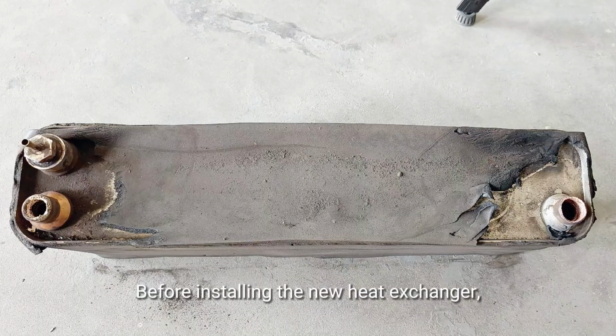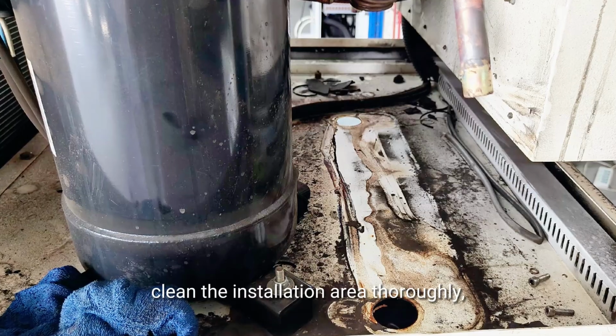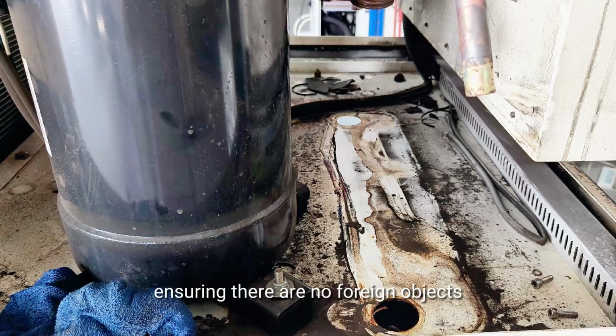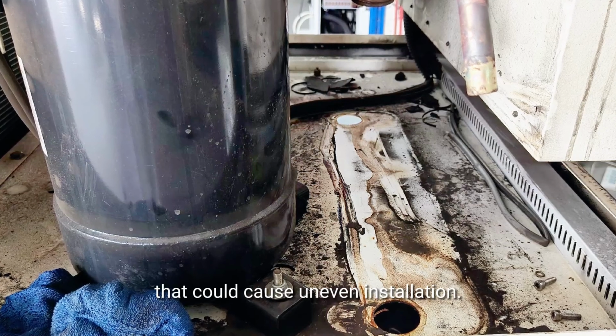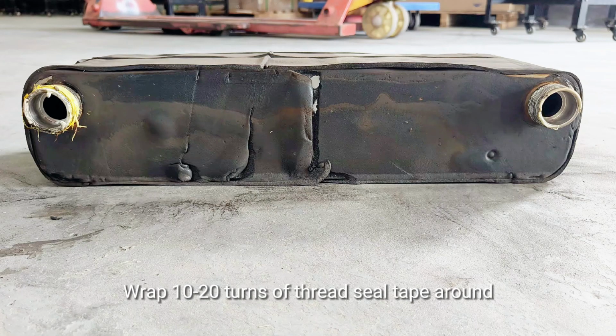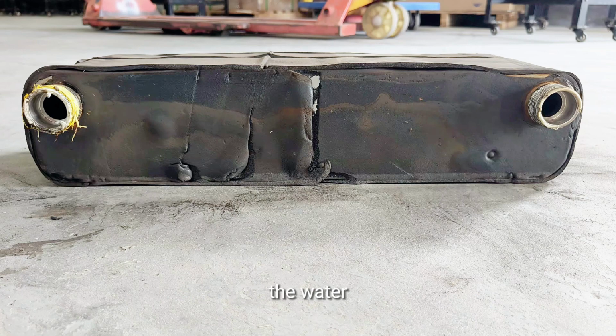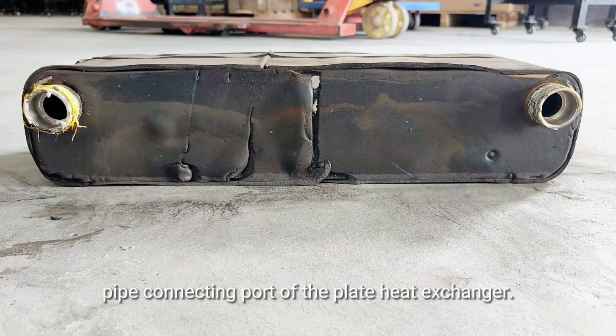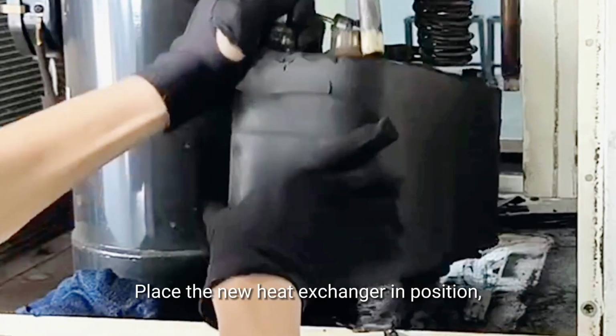Before installing the new heat exchanger, clean the installation area thoroughly, ensuring there are no foreign objects that could cause uneven installation. Wrap 10 to 20 turns of thread seal tape around the water pipe connecting port of the plate heat exchanger, then place the new heat exchanger in position.